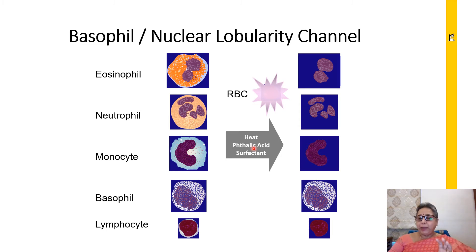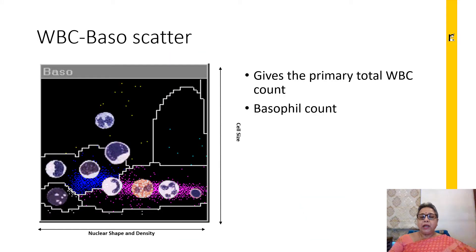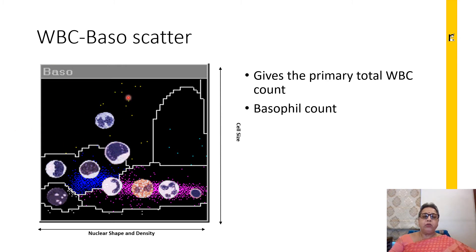The cytoplasmic membrane of the basophil is resistant to being stripped by acid, whereas all other white blood cells have their cytoplasmic membrane stripped and only the nucleus gets exposed. We then look at nuclear shape and density versus cell size. Plotting the nuclear shape and density — based on the lobularity of the nucleus — against the cell size gives another scatter where the basophils are counted.